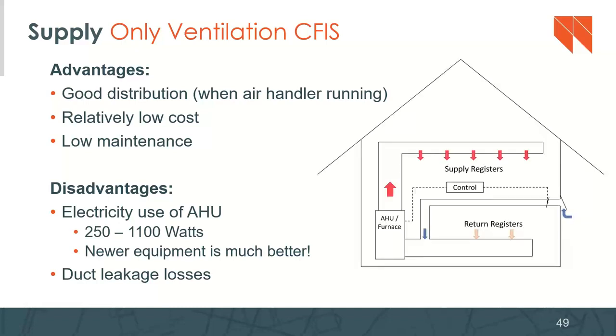So here's another diagram of what this system might look like. And so this is without a booster fan. It's just using this air handler, right? Fresh air brought in. Here's the control that's tied to the air handler. Typically, this control is going to tell the air handler to turn on and open the damper periodically throughout the day. There's smart controls out there that are going to integrate into the air handler where, if the air handler is running because it's hot outside and air conditioning needs to happen, it's going to do a calculation to reduce how often the air handler would run without a call for cooling. So there's that smart controller that's available.